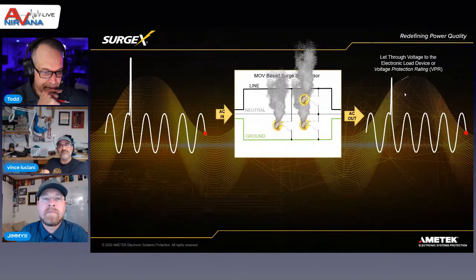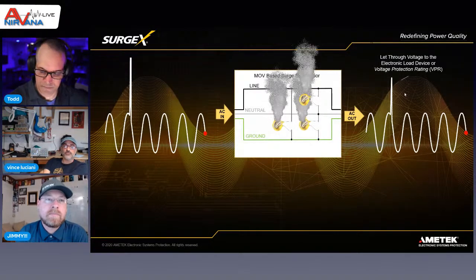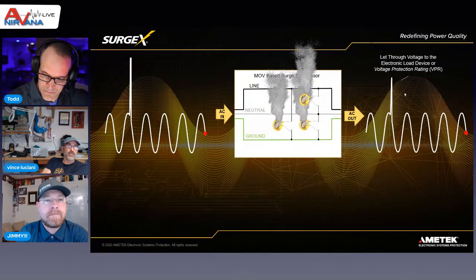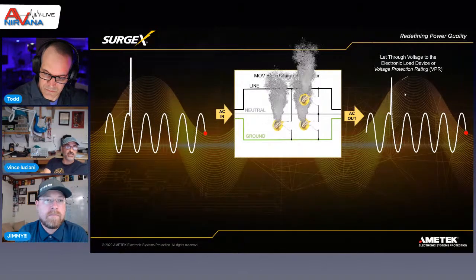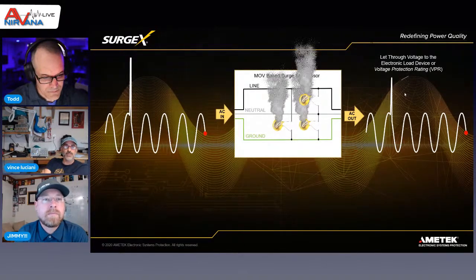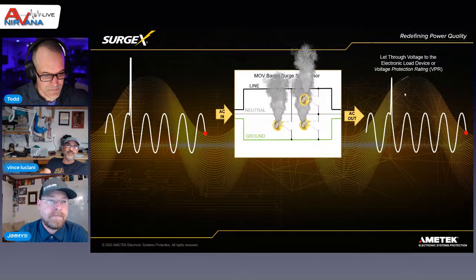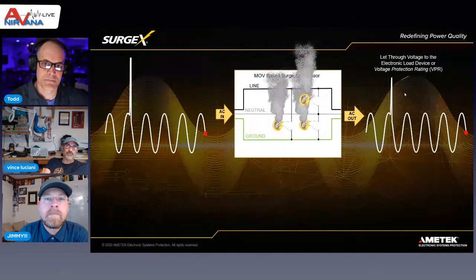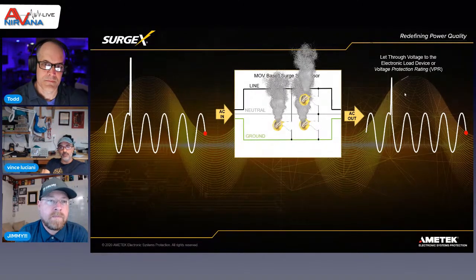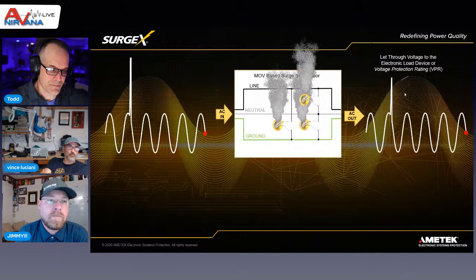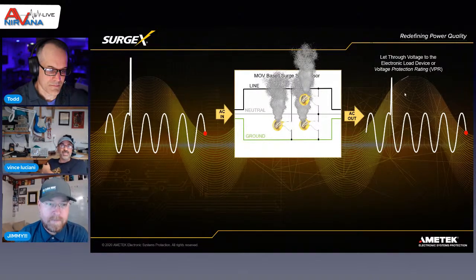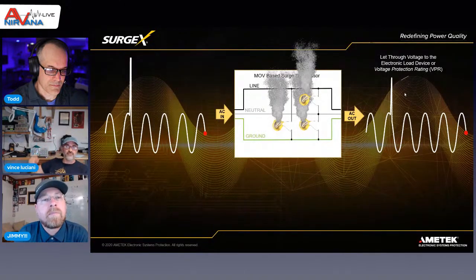If you have an MOV-based surge protector that has been UL approved to the UL 1449 standard, which is the standard for surge protectors, UL will put on there a voltage protection rating, or VPR. That's the amount of voltage that gets let through to the output if 6,000 volts are put on the input. Not that the sine wave is 6,000 volts, but if that surge waveform gets up to 6,000, what is the output?